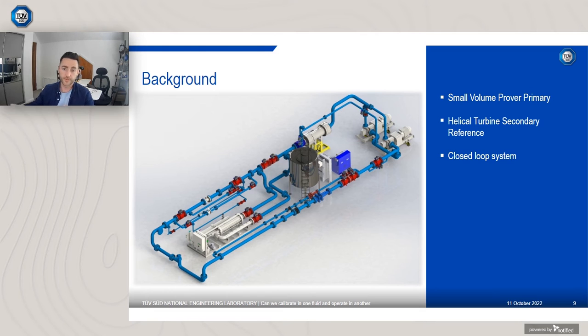It's a closed loop system, so as you can see we have a buffer vessel that fills the line once the device under test, so let's say a Coriolis meter, is installed in the test section here. The line is filled, we've got 2 main flow pumps, an inline heat exchanger, a pressurization unit to achieve the required pressure, and a heat exchanger for the required temperature. We flow round through the prover, through the required reference meter depending upon the flow rate, and then round depending on which test section the meter is installed, flow through and then continuously flow round. So a closed loop system.